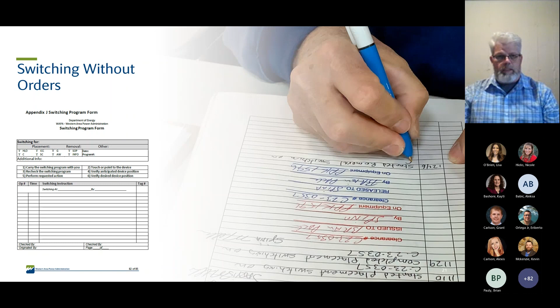One of the things we want to talk about is equipment limitations. Like I mentioned with pole switches, make sure the switch is designed to do what it's supposed to do, whether it's a pole switch, a disconnect switch, or whatever the case is. Make sure you operate the equipment within its limitations. For lines and transformers, we have disconnects on the high side sometimes that are made to de-energize the transformer. We have load break disconnects, fuse disconnects, and motor operated disconnects.